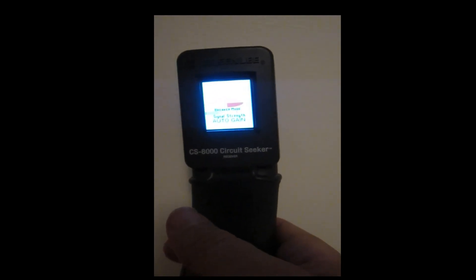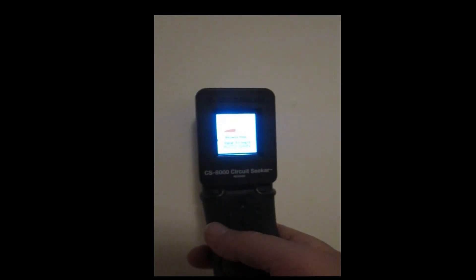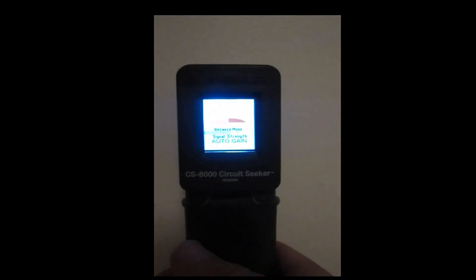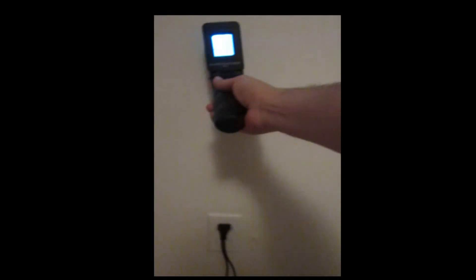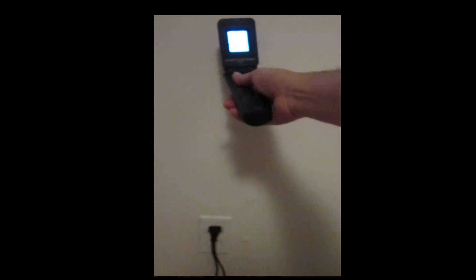So see the signal strength is highest right here. We're right above the circuit. As we scan over here off to the side, it goes down. It's high here right above the circuit. And down. See that? Highest there. Down. Highest there and down. So the circuit looks like it's going. And we still got a strong signal way up here. So the circuit seems to be going straight up in the air.